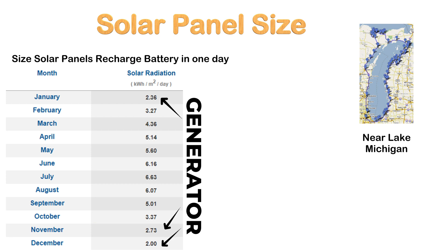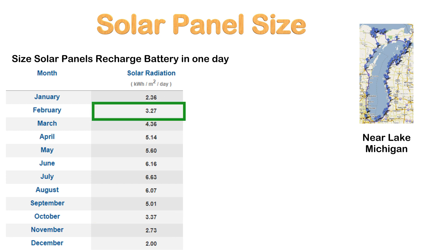In step 3, we need to size the solar panels needed to charge the battery in one day. We must figure out the sun hours for your location. For example, near Lake Michigan in Lansing, Michigan, a sun-hour chart shows that November, December, and January have the fewest sun hours. Sizing for those months would require more solar panels and increase cost. A generator can supplement energy during those low-sun-hour months. We'll use February, calculated at 3 sun hours, as our baseline.